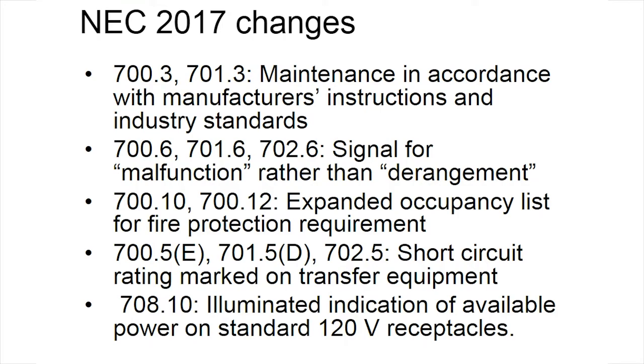700.6, 701.6, and 702.6 call for a signal telling that the system has malfunctioned. Now, for many cycles, that signal was called for to indicate the derangement of the emergency system. Since then, they've changed it to malfunction, and I see that as a good thing because we often wondered what derangement meant in this context.